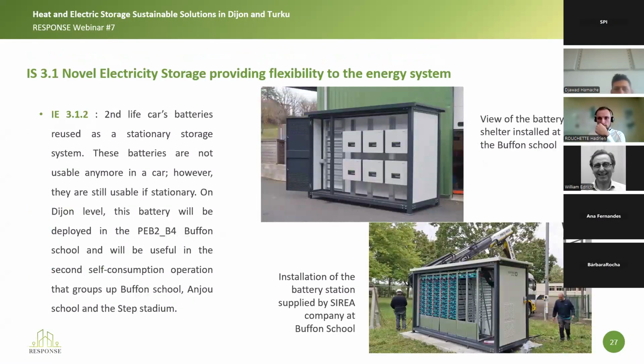Next slide please. This is the battery station as supplied by the SIREA company and installed and commissioned at Dijon school. It contains 7 battery racks with 80 kilowatt hours per rack, and 7 DC-AC inverters to convert the energy from direct current to alternating current. Each DC-AC inverter is 20 kilowatts. The system was installed and commissioned in October 2024.